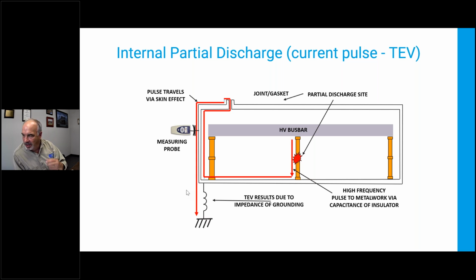And so what I'm going to do is measure that voltage with a voltmeter. A very fancy voltmeter, I'll give you, but it's got a capacitive probe in the front. Your body and your hand holding onto it forms a capacitive sink as the other lead of the voltmeter. And this voltmeter has to be able to sample in the nanosecond range to pick up these things that are microseconds long, pick up waveforms, measure the peaks, capture the waveforms, capture the phase resolved plot, do all that at these really high speeds and really low levels, measuring microvolts that are microseconds long, and I'm doing it in the presence of hundreds of thousands of volts and hundreds of megawatts. So it's not the easiest thing to pick out, but the right instrument will grab that for you.